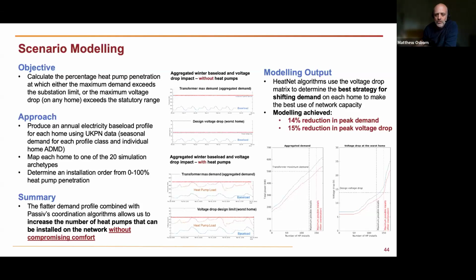So we set about trying to calculate the best possible heat pump installation sequence to limit the impact of voltage drop in order to hit the capacity limit, since we hit the voltage drop first. Ultimately, by using a controlled installation sequence to limit voltage drop before hitting capacity, we found that combining Passiv demand flattening—our control technology—with our prototype HeatNet coordination algorithms, we could install about 30% more heat pumps using the same network infrastructure.